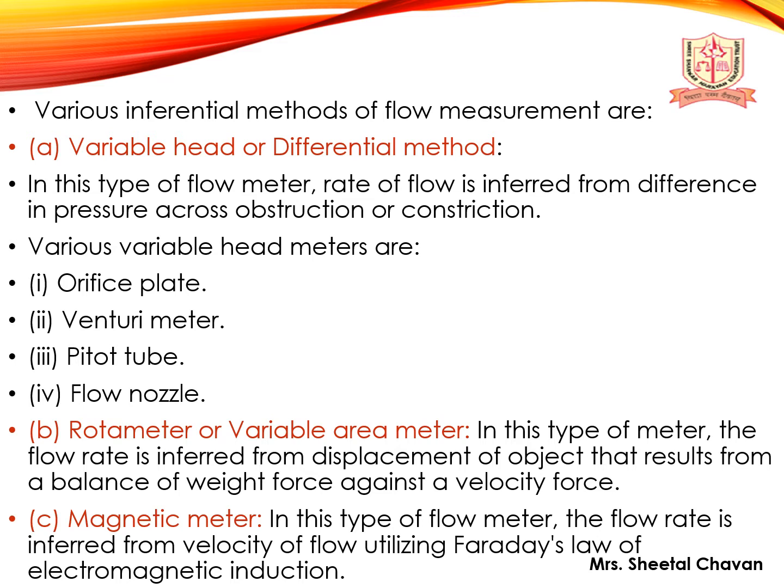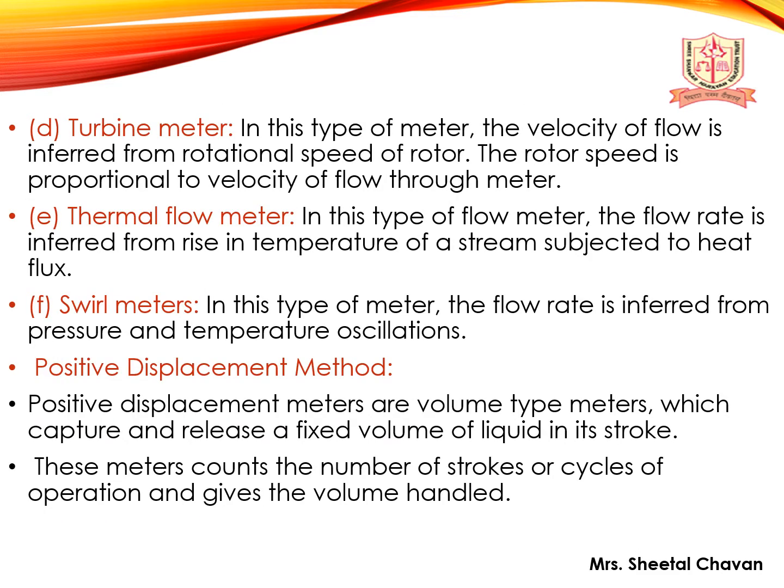The second type is the rotameter or variable area meter, where the flow rate is inferred from the displacement of an object that results from a balance of weight force against velocity force. The third is the magnetic meter, where the flow rate is inferred from the velocity of flow utilizing Faraday's law of electromagnetic induction. The fourth is the turbine meter, where the velocity of flow is inferred from the rotational speed of a rotor, which is proportional to the velocity of flow through the meter.